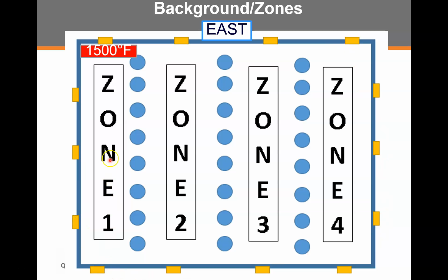And what we're seeing is we're taking temperatures, and you can see this background temperature is 1500 degrees. Now, suppose this operator sets his camera at 1500 degrees for background and 1 emissivity for all of the tubes. Now, that's fine, and that's going to give you a temperature correction, but is it accurate? Because what we're trying to say by doing this is this background is going to affect not only all these tubes, but all of these tubes. But in real life, what we found is all these backgrounds are actually slightly different.